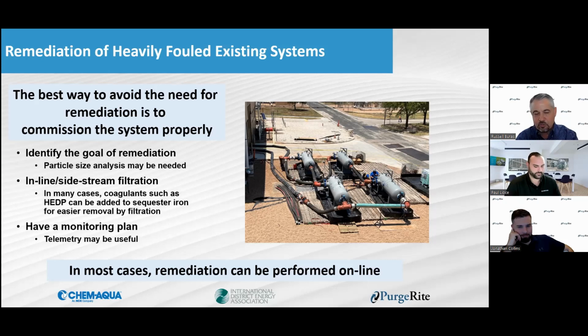We've seen situations where a district plant could not shut down, but had a super high iron content of say 8 parts per million, and they wanted to reset their system. In that particular case, they actually had a sand filter in place. Some will have air dirt separators, but the system literally gets away from them for whatever reason, not chemically maintaining it over the years, adding a bunch of new things that get shoved into the system.